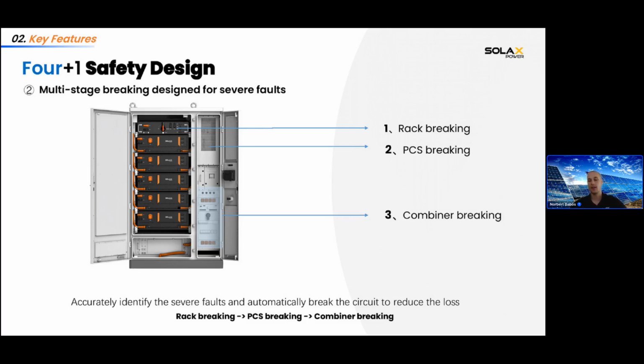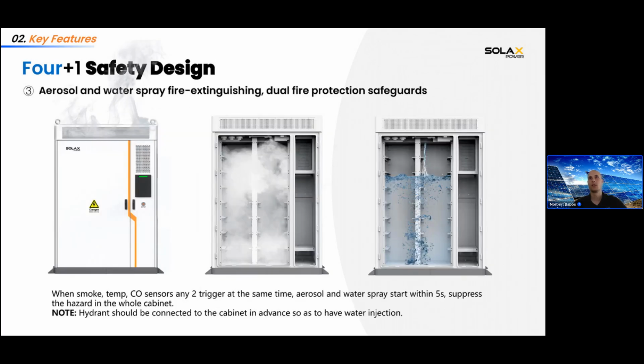And if that is still not enough, then comes the third level, which is the aerosol and water spray inside the cabinet. If there is still smoke or heat or CO sensors triggering an alarm, and even the breaking did not solve the problem, it will trigger the aerosol and the water spray inside the cabinet in order to suppress the fire, the smoke or the overheating. For that, you must have a fire hydrant connected to the ESS to have a water supply for the spraying. So that's the third level.